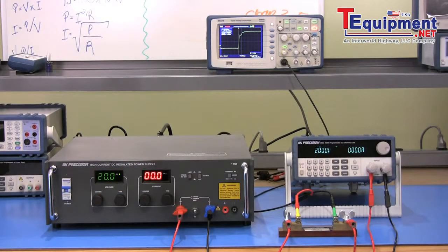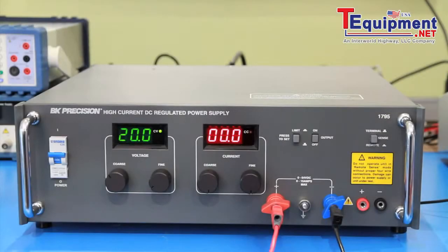Now, we need to configure all the instruments for the setup to measure properly. On the power supply, set the output voltage to 20 volts and the current limit to slightly above 15 amps, so that the power supply can maintain a constant voltage mode at maximum current draw by the load.